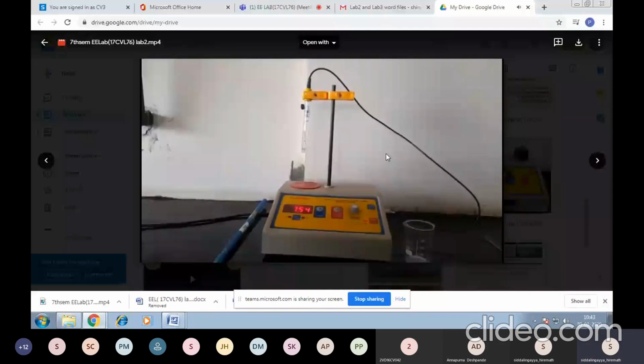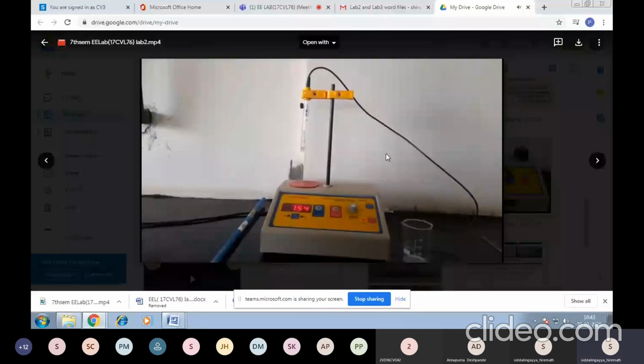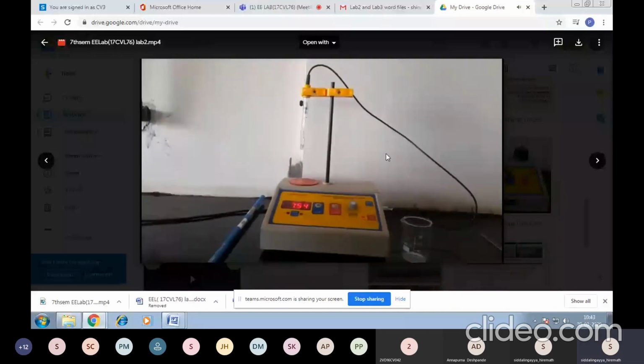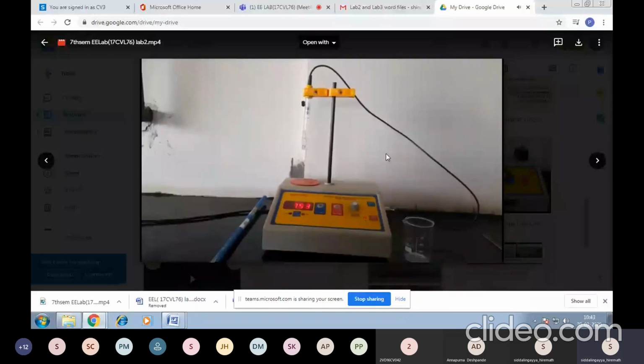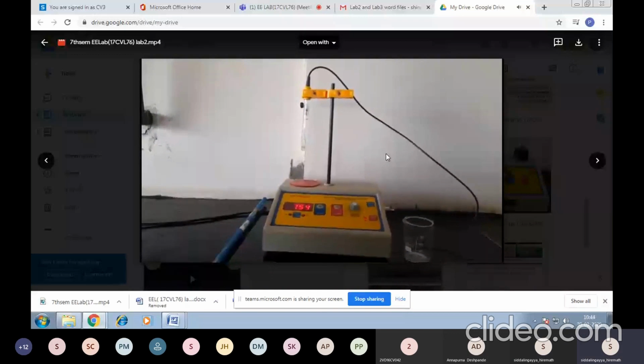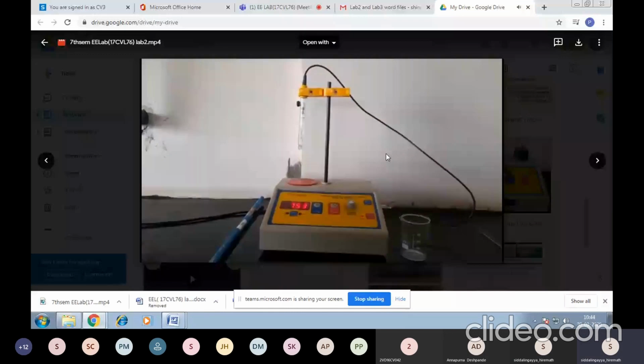So let me discuss the interfering factors here. At pH values above 10, so-called alkali errors may occur. In such cases, the use of an alkali-resistant electrode is recommended. Changes in glass structure can occur in older electrodes, so that errors may appear when measuring weakly buffered water. In such cases, the electrode should be renewed.